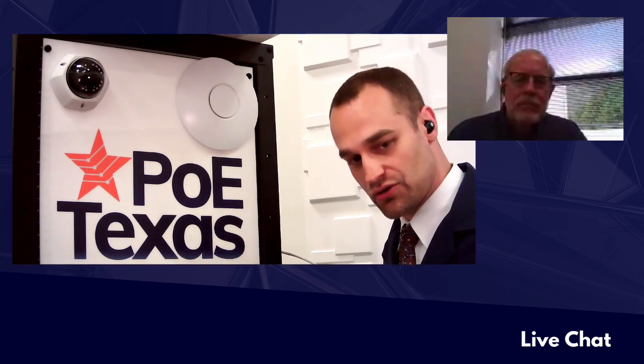That polarity is important because not all devices will operate with both polarities. So another troubleshooting tip I'd give is if you're looking at a device that's unstable or won't power up, give it that mode A-B check - really quick and easy to do when you've got the right tools. The next thing I'd suggest is double check your polarity. Usually it's called out on the data sheet, the polarity of both your powering device, the PSE, and the PD. We see that a lot.